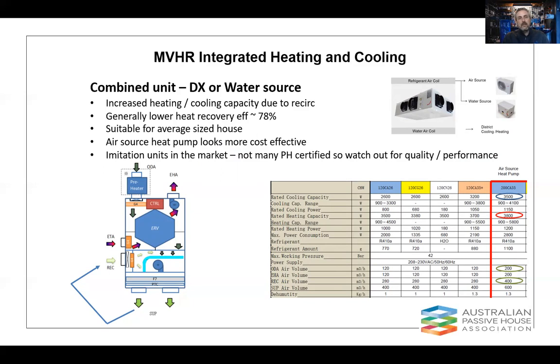Now, one of the things that has always been a capacity limit for delivery of heating and cooling has been the fact that the airflow of the HRV unit has really dictated the amount of capacity for heating or cooling. And it's typically, for a 350 cubic metre per hour unit, which is about 100 litres a second, the capacity has really been 2 to maybe 3 kilowatts tops on heating. And that has been a little challenging in most projects, even certifiable passive houses. It tends to be fairly marginal.